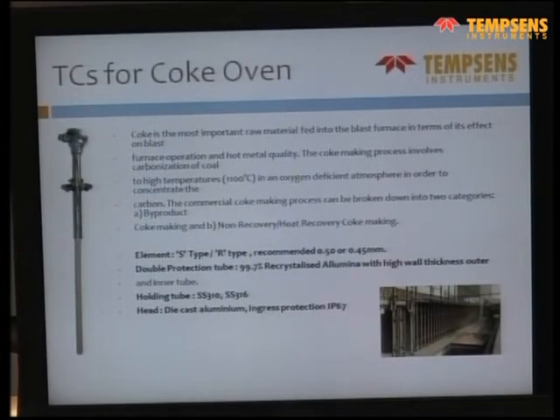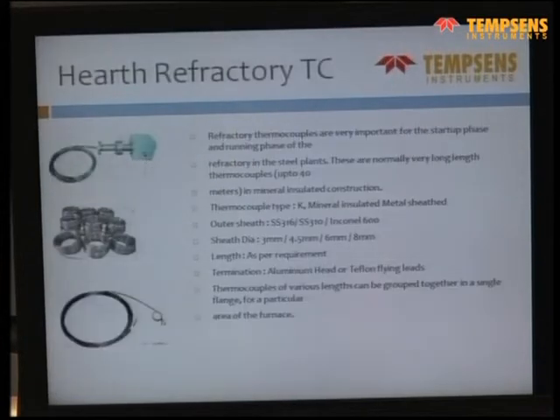For coke oven it is again a similar kind of thing, with a double ceramic tube, and it is used for coke oven battery application. These are long length, up to 2 meter long thermocouples for such cases. Then these are for the refractory thermocouples. For steel plant refractory, the first one, as you see in the box, is a multi-point thermocouple. There are different positions in the refractory. Sensors are laid inside the refractory and it gives the temperature at different points and different levels in one box. Second are the thermocouples for different lengths. Normally it is K-type with Inconel sheathing or 310 sheathing, used for all steel plants.